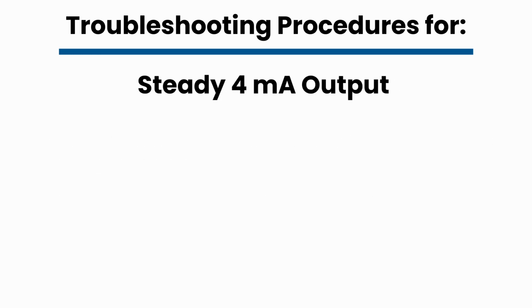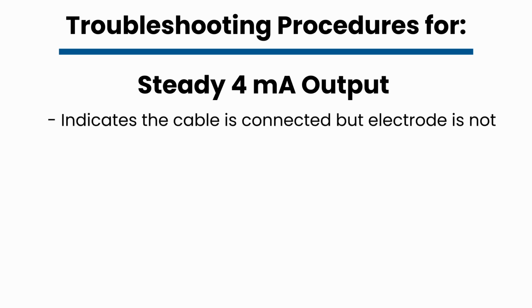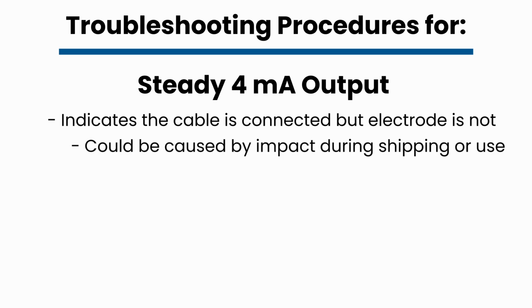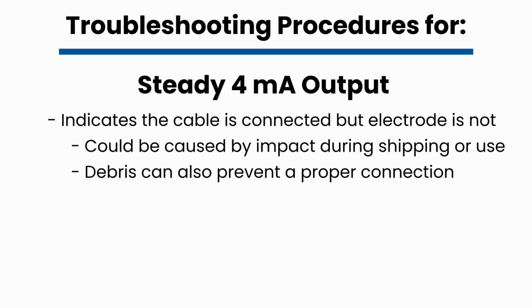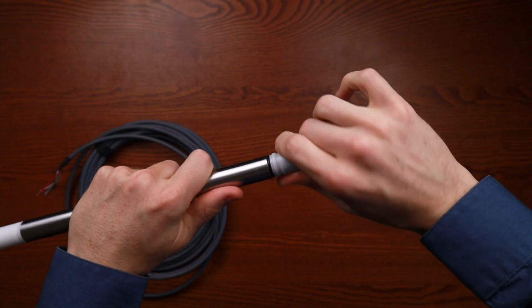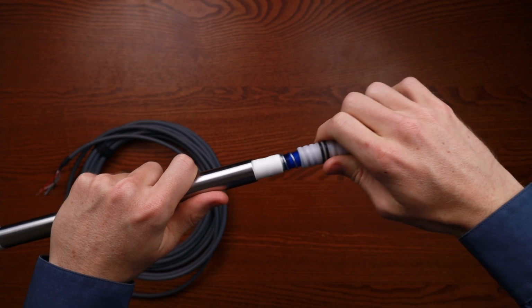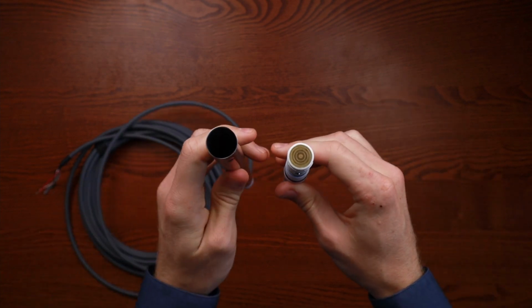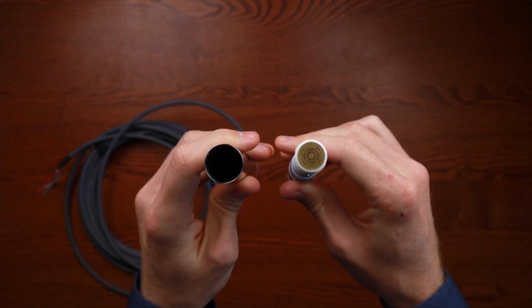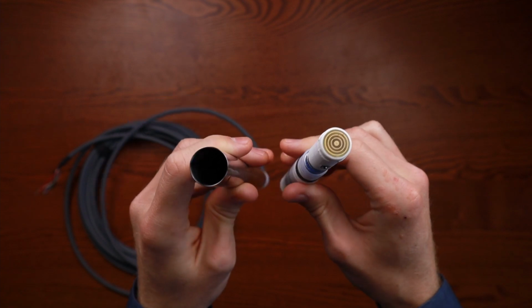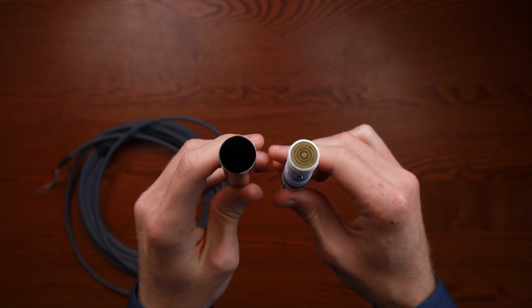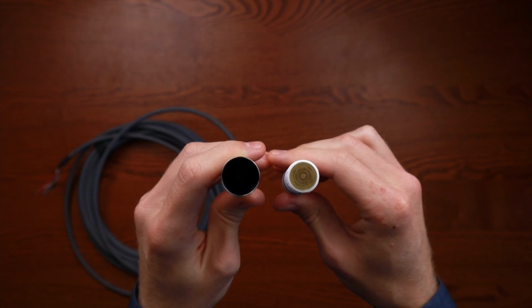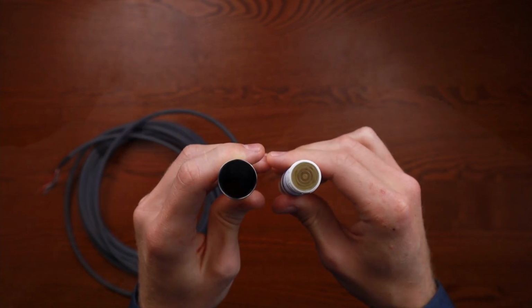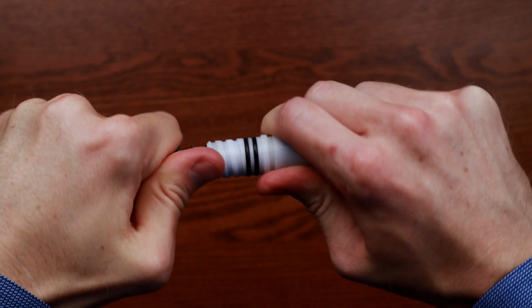A steady 4 milliamp output indicates that the cable is connected to the circuit board, but the electrode is not, which could be caused by impact, during shipping or use, or if debris has entered the sensor. To fix this, start by unscrewing the electrode. As mentioned before, wrapping a rubber band around the plastic body may help if you find your grip slipping. Examine the electrode connector to see if anything may be obstructing a connection. Look inside to check the circuit board connector is clear and free of damage as well. Once removed, gently twist while pulling to take the electrode out.